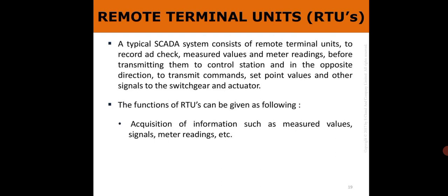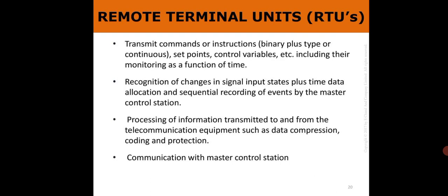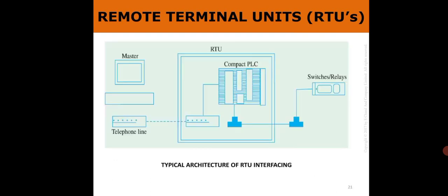Acquisition of information such as measured values, signals, meter readings, etc. Transmit commands or instructions in a binary pulse type or a continuous type. Set points, control variables, etc., including their monitoring as a function of time. Recognition of changes in a signal's input state plus time data allocation and sequential recording of events by the master control station. Processing of information transmitted to and from the telecommunication equipment, such as data compression, coding and protection. Communication with a master control station. This is the architecture of RTU interfacing.